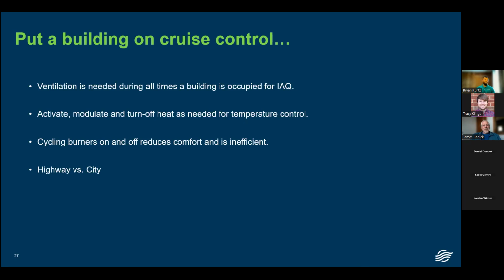You don't want to cycle. What we do is we activate, modulate, and turn off heat as needed for temperature control. Typically, on a winter day, it's going to start up. And what happens in the building when people are in it? You need ventilation. A huge example of that was during COVID. What was the best way to improve air quality inside the building? That was to bring in more outside air and flush the nasties out.